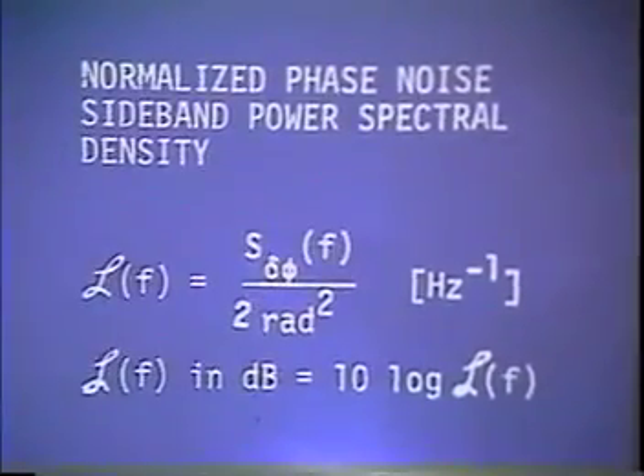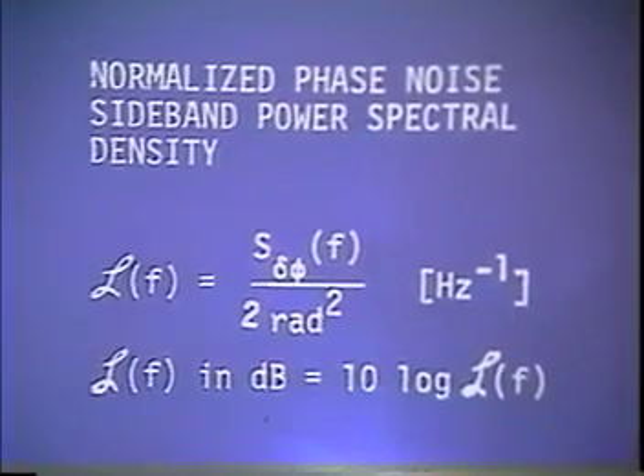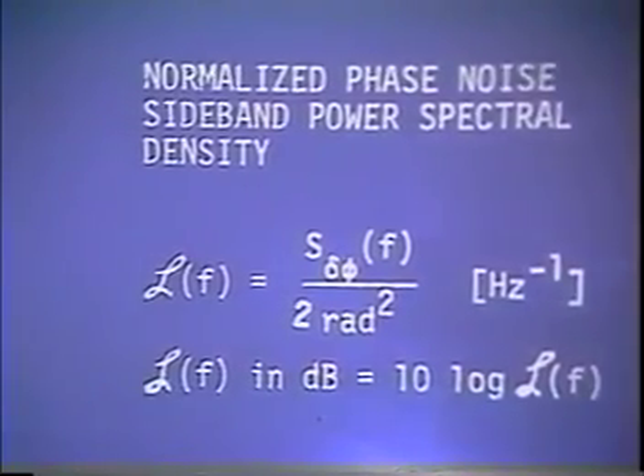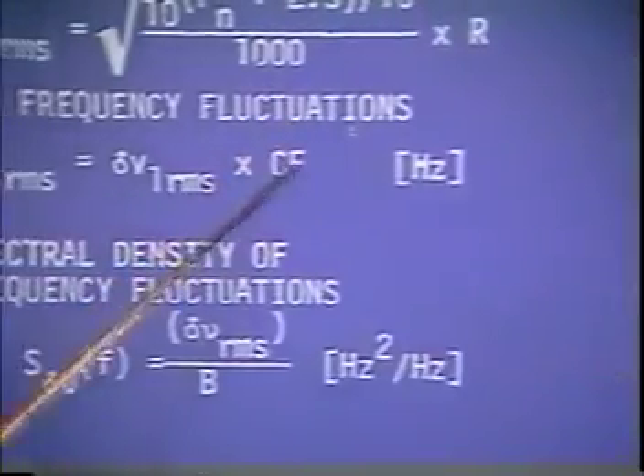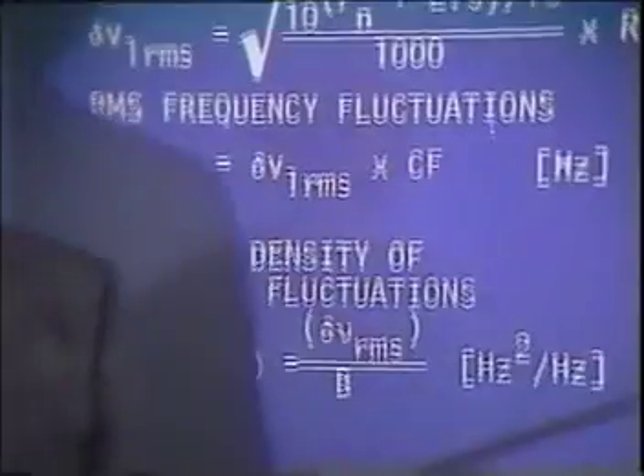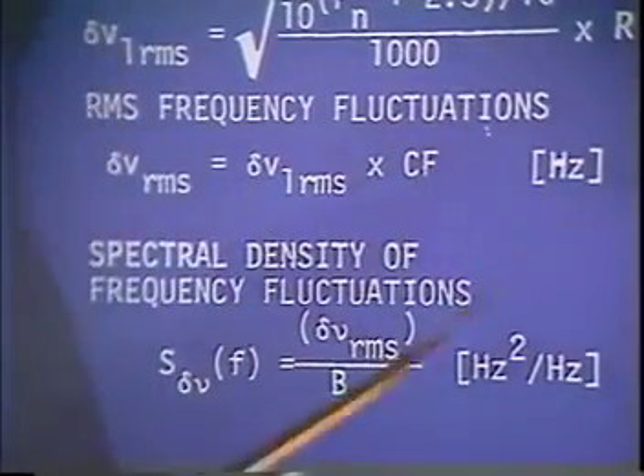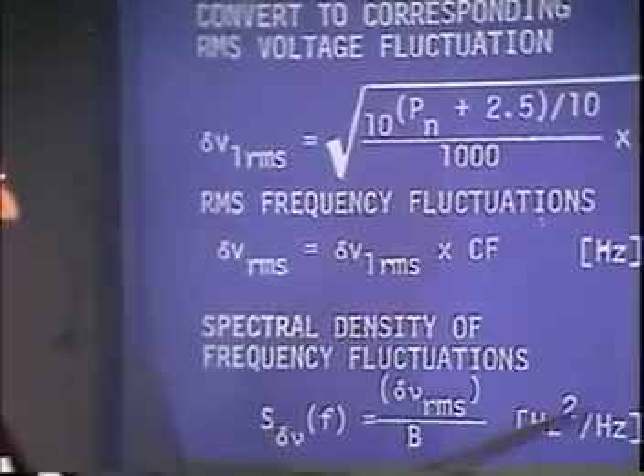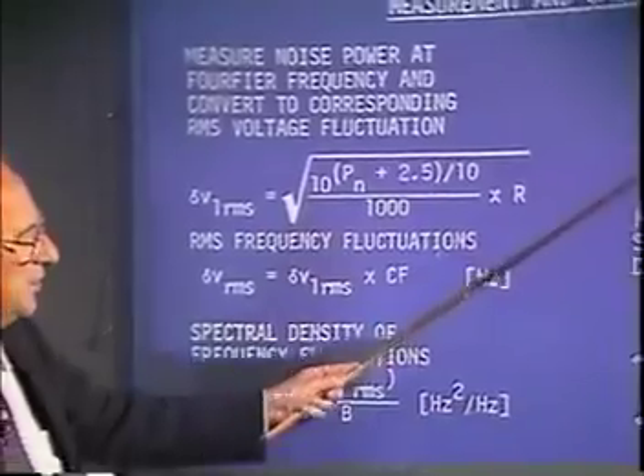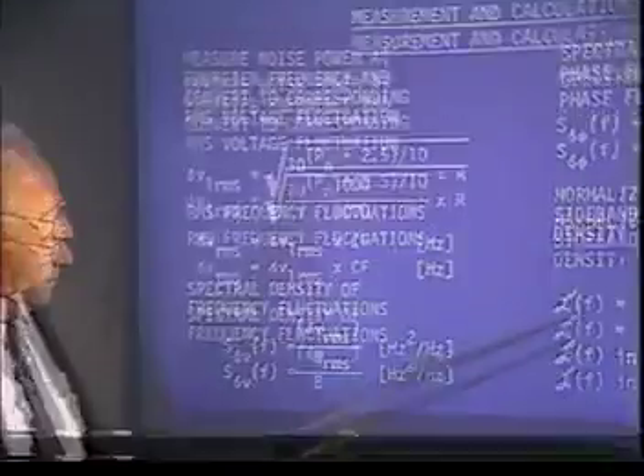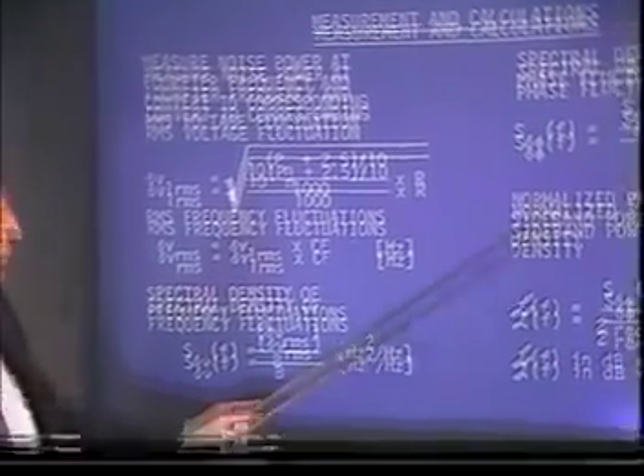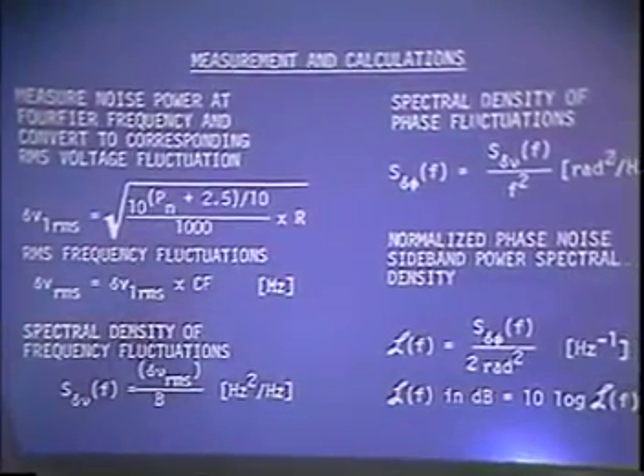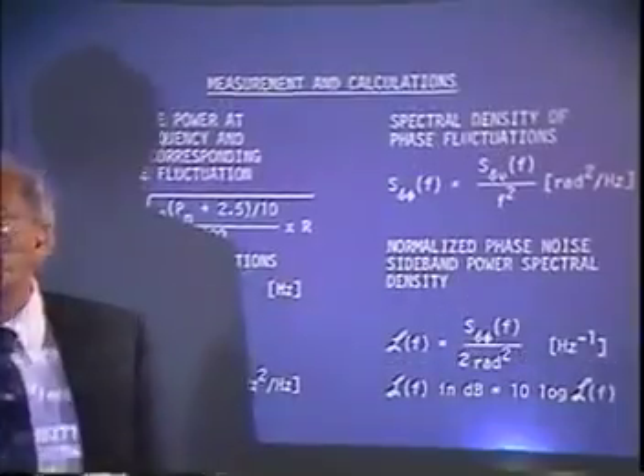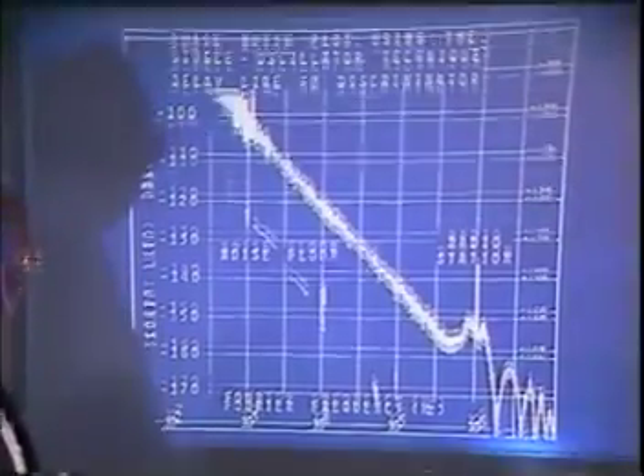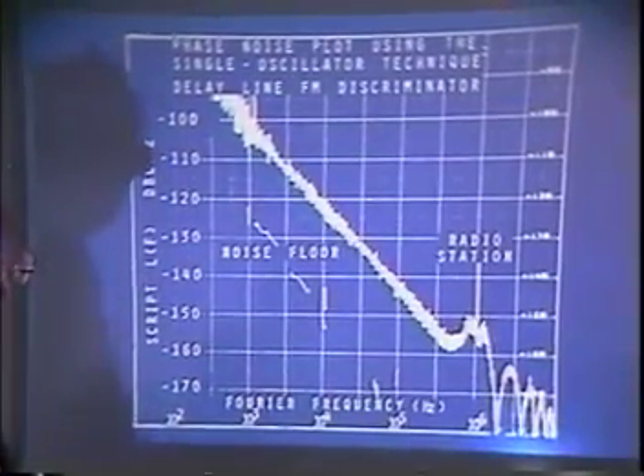Now this is something that's done in the system downstairs, and so that's the mathematics you will have. First you calibrate the frequency discriminator, then you measure the voltage and multiply by that factor, and you know now exactly what kind of spectral density you have. Because once you take into account the bandwidth at which you made the measurement, then you know the spectral density. Once you know the spectral density, you can convert that to phase spectral density and then to script L of f, which is the normalized phase noise sideband power spectral density. Then that's plotted. When you plot it, this is what the plot will look like.